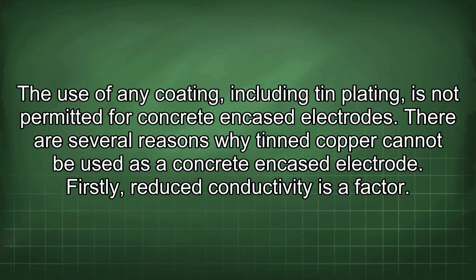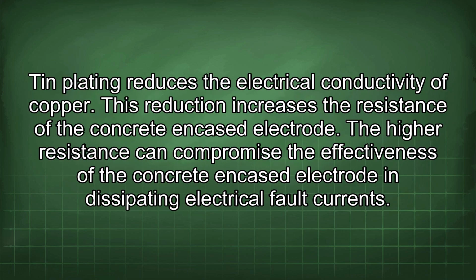There are several reasons why tinned copper cannot be used as a concrete encased electrode. Firstly, reduced conductivity is a factor. Tin plating reduces the electrical conductivity of copper. This reduction increases the resistance of the concrete encased electrode. The higher resistance can compromise the effectiveness of the concrete encased electrode in dissipating electrical fault currents.